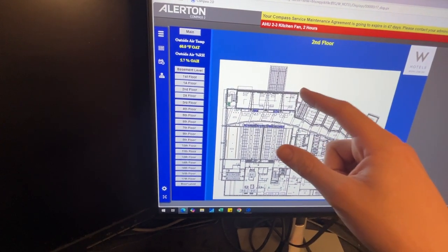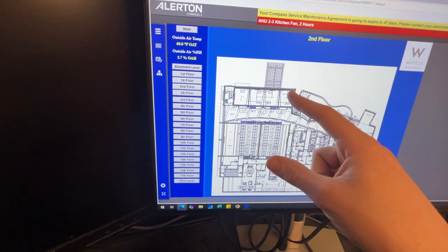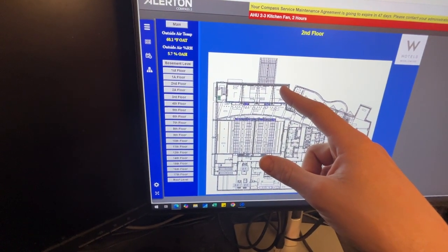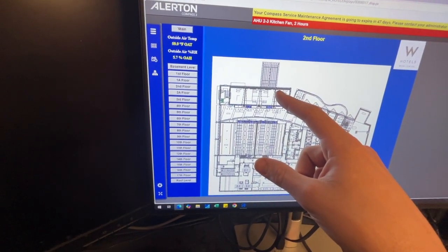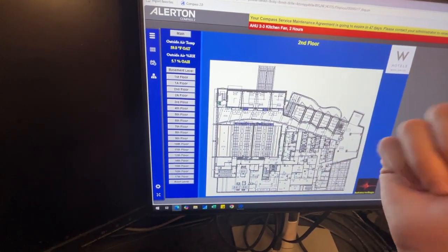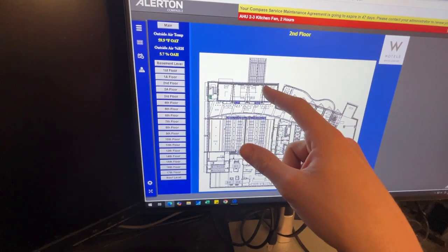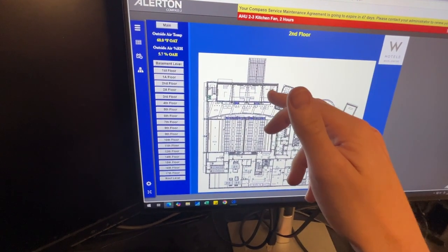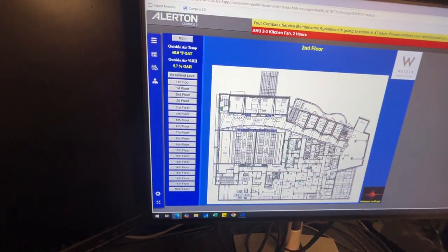Those should not be responsible for the whole heat in that room. All they're for is freeze protection so that it doesn't get extremely cold by your windows. So those should be set really low, to like 64 degrees. If we get below that, then they kick on and allow heat to come through. Reason being, if these are in charge of providing all the heat to these rooms and they open every time somebody wants it to be warmer in there, they hammer.